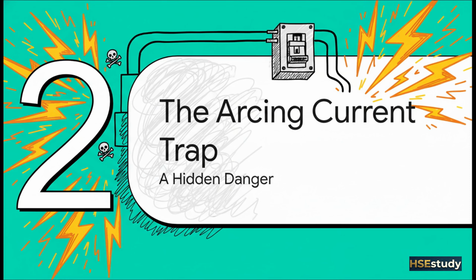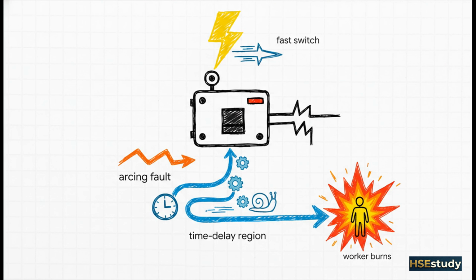This is an incredibly dangerous phenomenon, where a standard, everyday, low-voltage breaker completely misinterprets a deadly arc flash and thinks it's just a normal day at the office. So here's the engineering. An arc has to jump through open air, right? And that air gap acts as a resistor, which can drop the fault current just enough so that it doesn't hit the breaker's instantaneous trip setting. So instead of tripping in milliseconds like it should, the fault gets pushed onto the breaker's time delay curve. That curve is designed to let big motors start up without causing a nuisance trip.